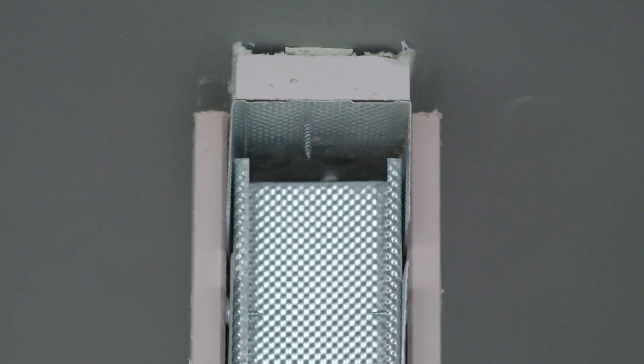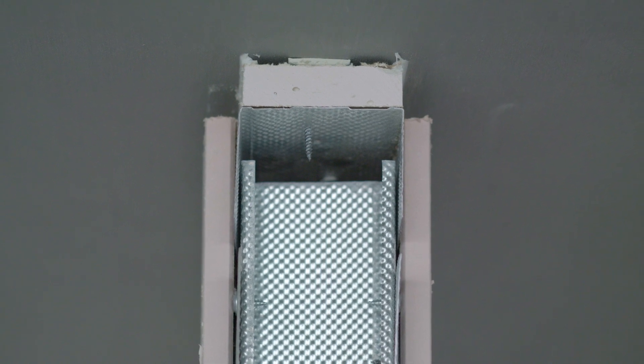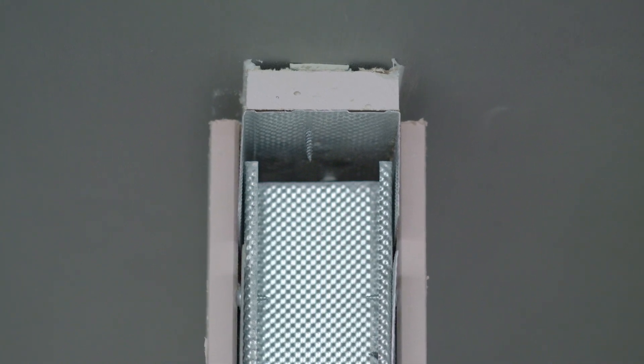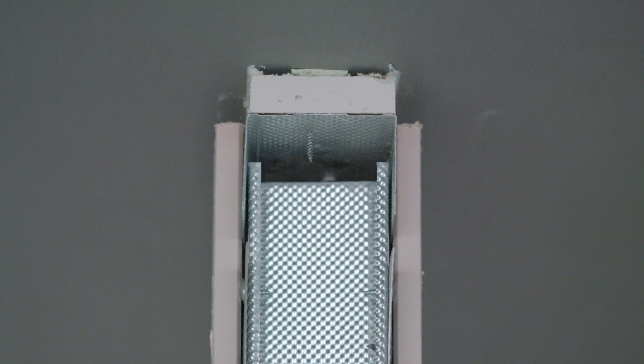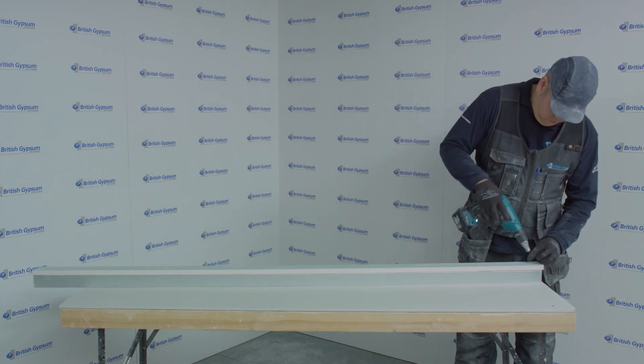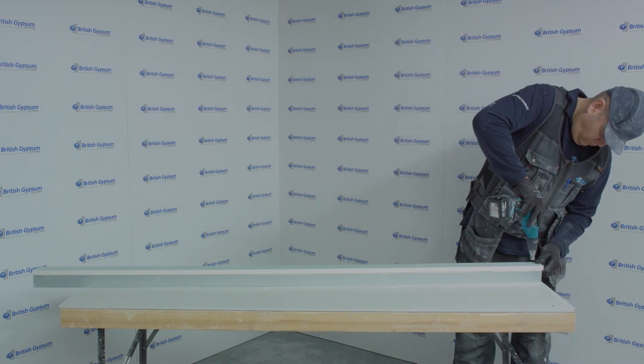For the purpose of this video, we'll be installing a 15mm downward deflection head with a 60 minute fire rating incorporating single layer 15mm fire line plasterboard. Step 1: cut and fix 19mm Gyproc CoreBoard to the back of 72 DC 60 channel with 35mm drywall screws.